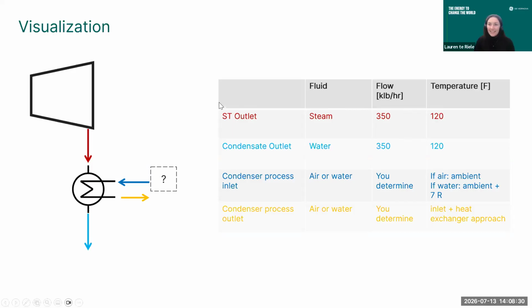It's typically in steam or water tables, and if it's not in your textbook, it's easily Googleable. That's a function of temperature and pressure, or maybe just temperature. Based on that latent heat as well as your flow rate, you'll be able to determine the energy you need to reject, but that will be a fixed number.